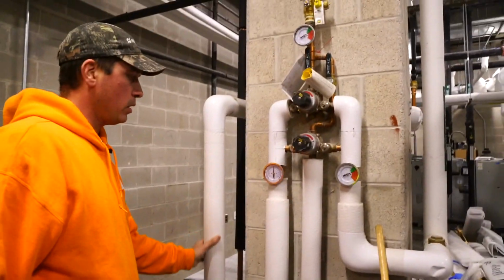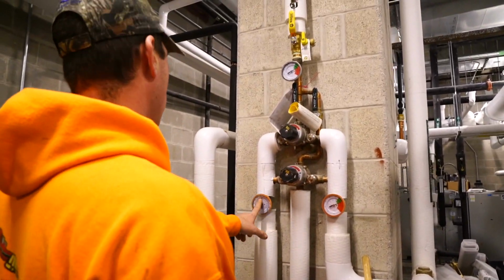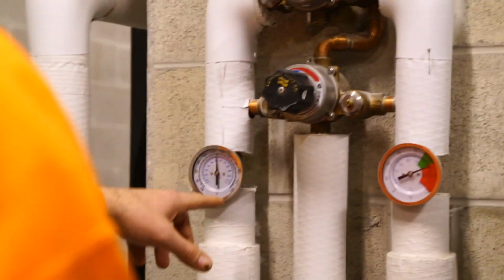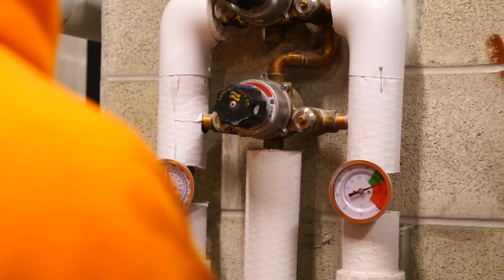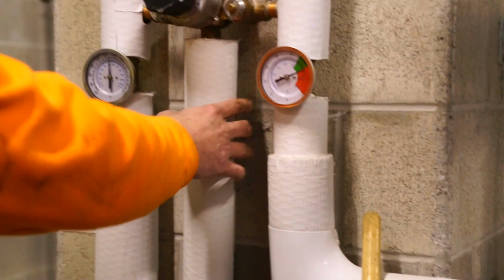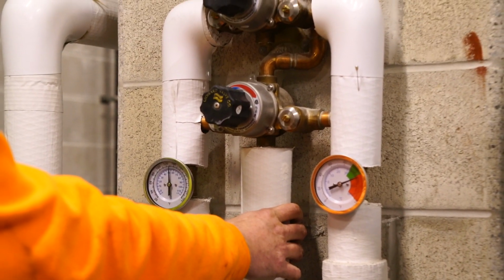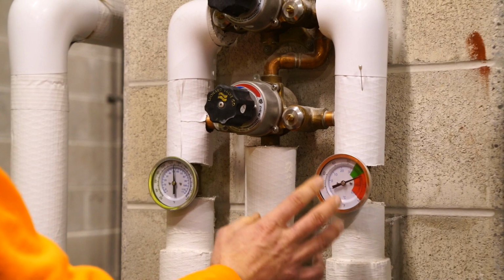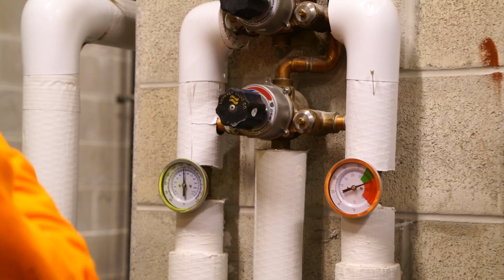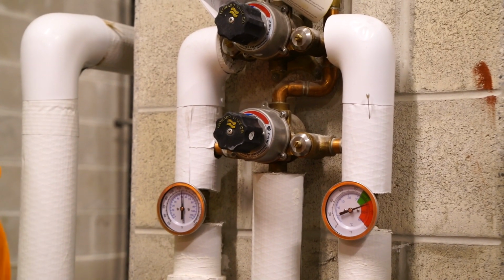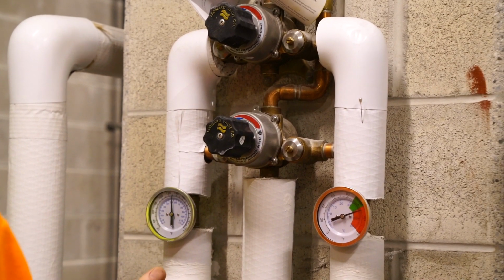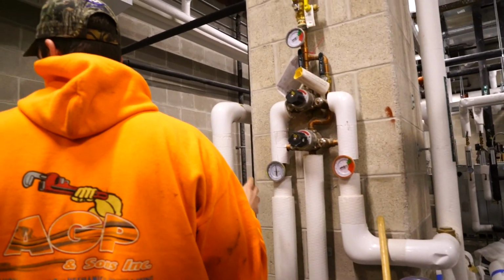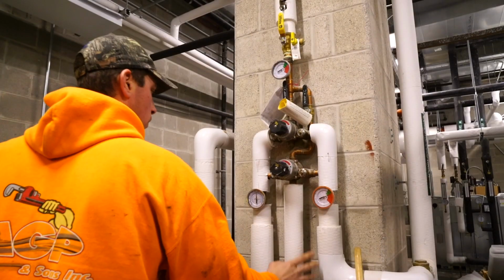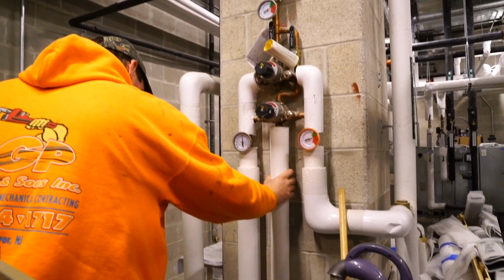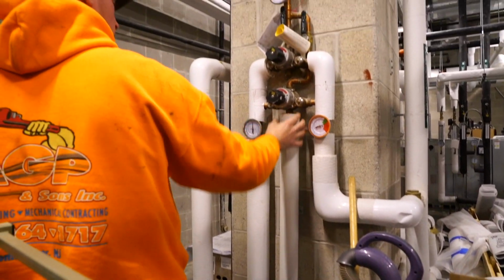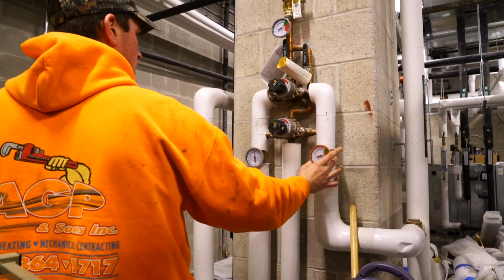So this is your hot coming in on your mixing valve side. Again, right here you can see that's coming in at 130, just like that other thermostat showed coming out of the hot water heater. Dumping into your cold side of your mixing valve is cold water, and then also the recirculation line that recircs hot water throughout the building. Actually, some of that dumps into here too. So we're not just always shooting hot water, it's more efficient. So right here is your recirculating line water coming in, and this is your cold side coming in.